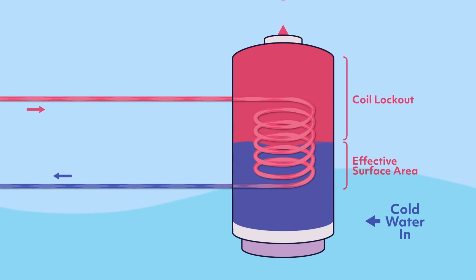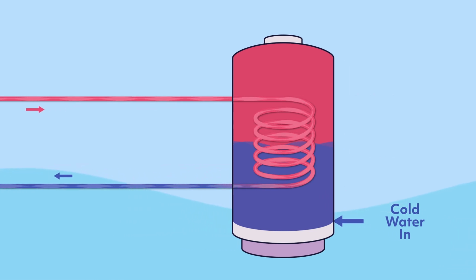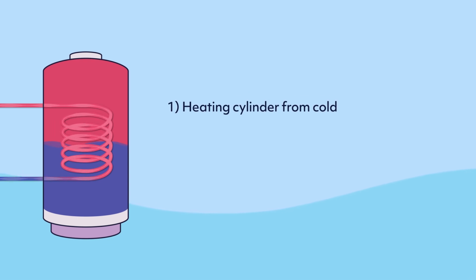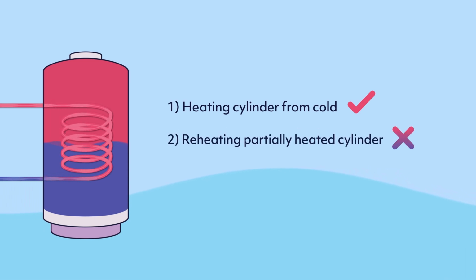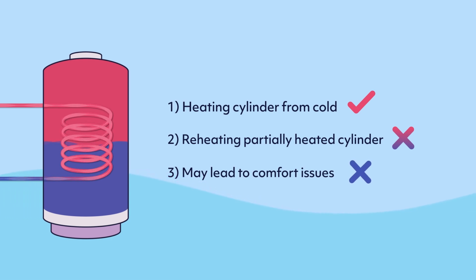As the heat pump tries to heat the water in this partially heated state, the system loop temperature has to increase, reducing the overall COP of the system. So, to summarize: 1. A large coil delivers good performance when heating the cylinder for the first time from cold. 2. However, when reheating a partially heated cylinder, the overall COP, or efficiency, is worse. 3. Some heat pumps slow down the heating when they detect this high thermal resistance, but this makes the heating process slower and risks causing comfort issues on a cold day.